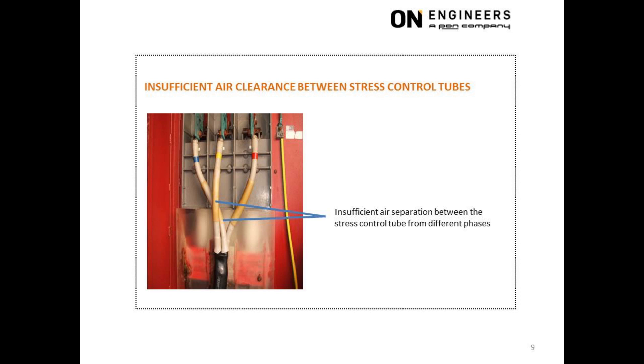This picture shows insufficient air separation between the stress control tubes from different phases of the cable termination, resulting in partial discharge at the surface of the stress control tubes. In this example, there is little room to move the stress control tube higher up and towards the cable lug.